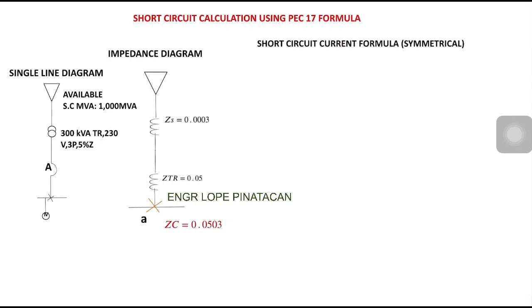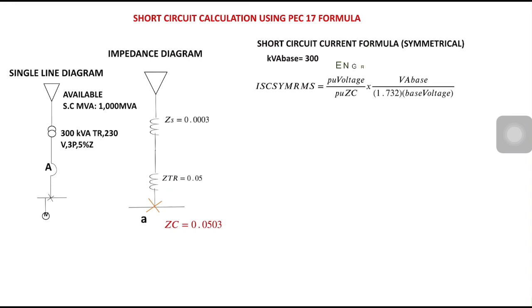So we need to know the short circuit current at this point. So we have the formula, we will get it from the Philippine Electrical Code 17. So we have given kVA base, assuming 3 phase equals 300. And then this is the formula: the per unit voltage divided by the per unit combined impedance times the kVA base, what I mean at the top is kVA base, and then divided by 1.732 times the base voltage. So we will replace all of this formula with the given values. So the per unit voltage is 1, and then the combined impedance is 0.0503, and then we will multiply it by the kVA base.